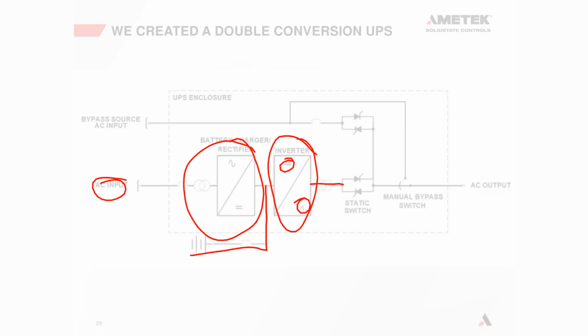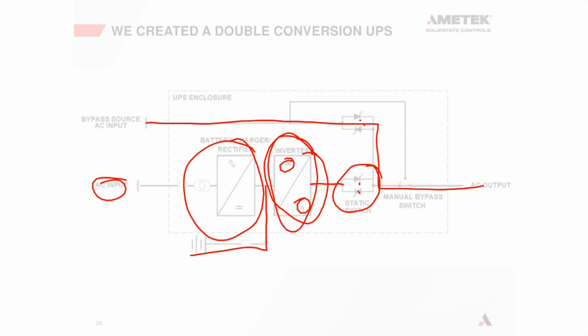That then goes through a static switch. If you want to know what a static switch is, you can watch some of our other videos that we have on our YouTube channel, and it goes into detail about what a static switch does. But basically, it's a switch that has no moving parts and can choose between the best source of power. And it does everything it can to basically always stay on inverter unless the inverter fails. And if the inverter fails, it will then transfer to an alternative source. Okay, so that is a double conversion UPS.